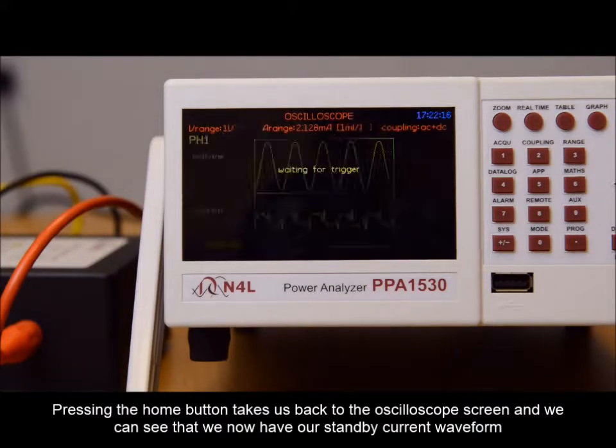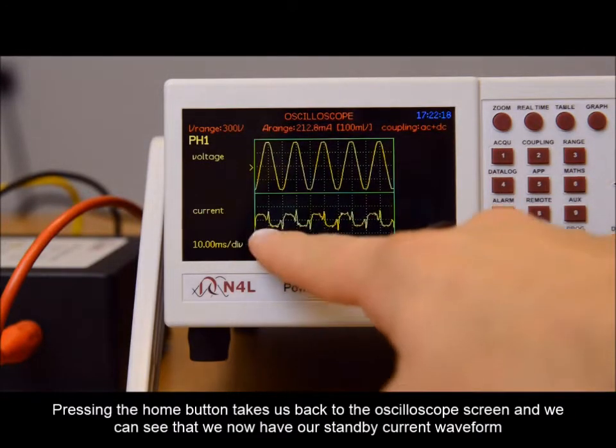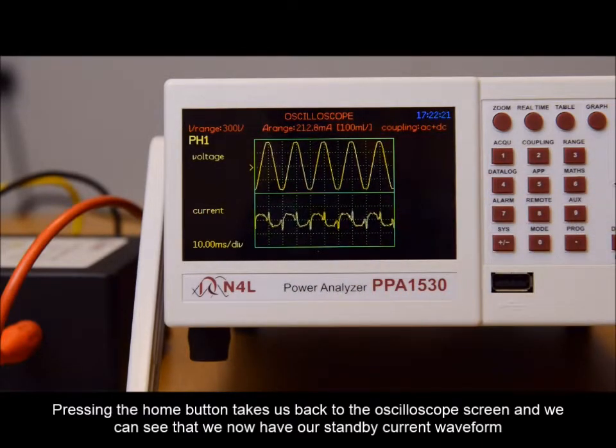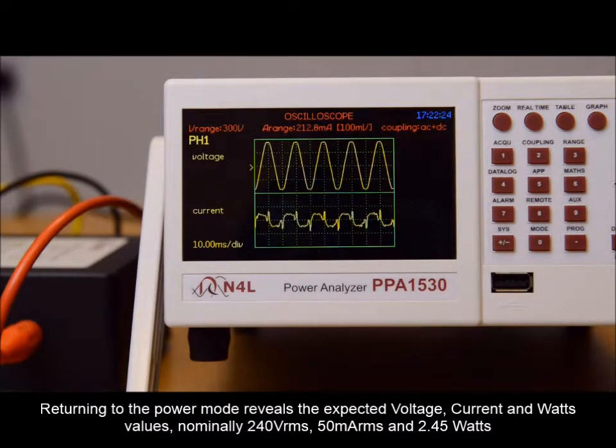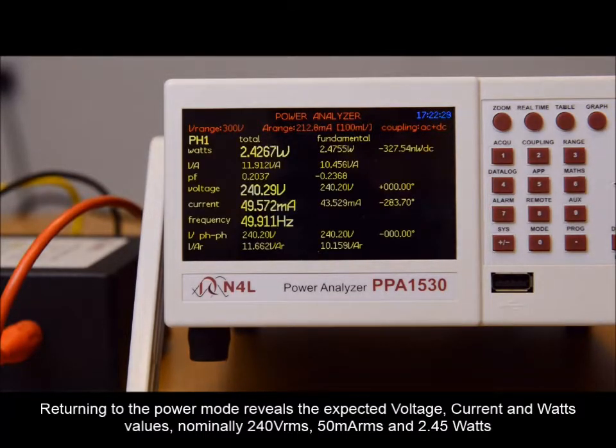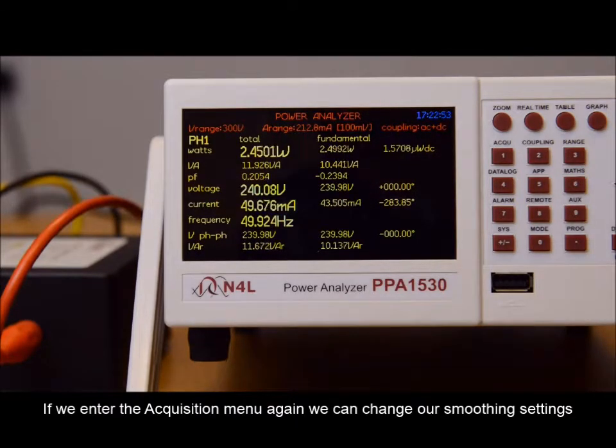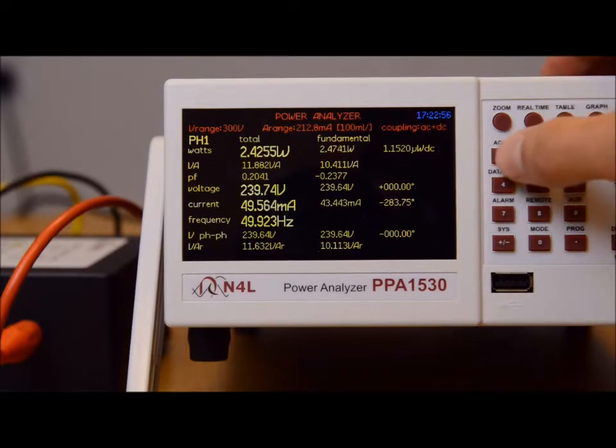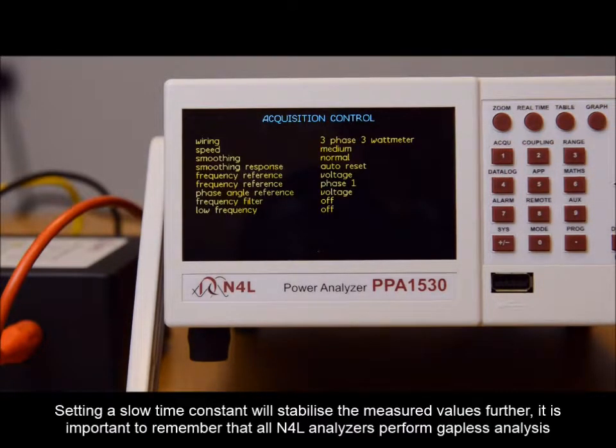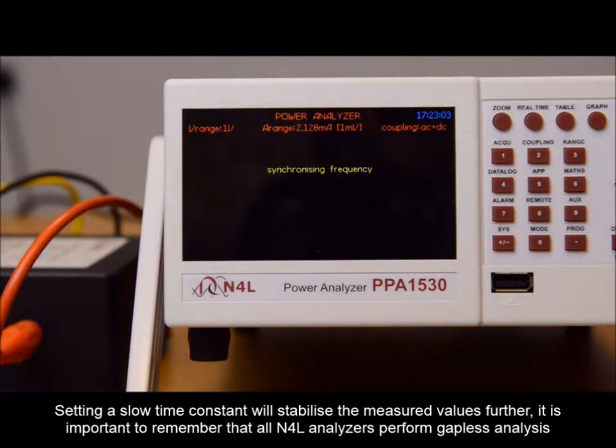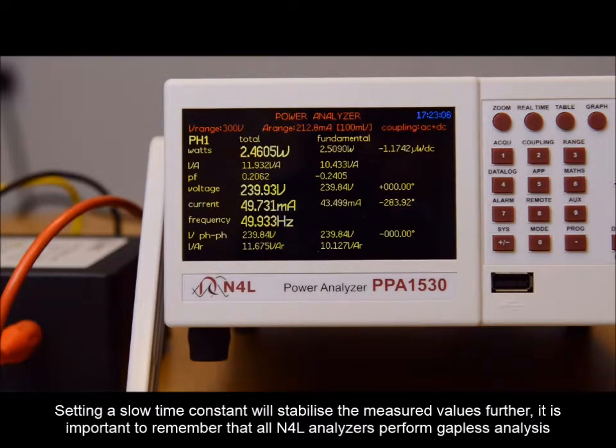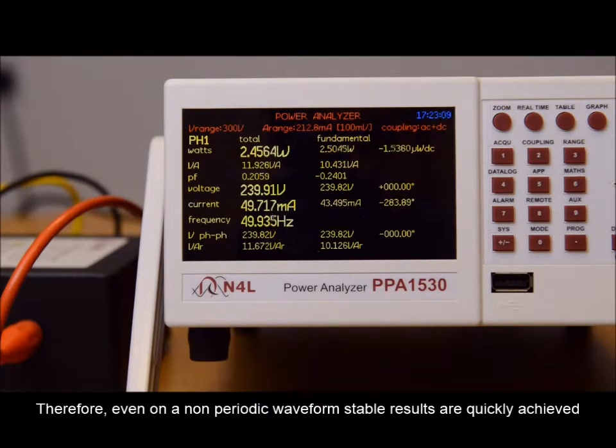Pressing the home button takes us back to the oscilloscope screen, and we can see that we now have our standby current waveform. Returning to the power mode reveals the expected voltage, current and watts values, nominally 240 volt RMS, 50 milliamp RMS and 2.45 watts. If we enter the acquisition menu again, we can change our smoothing settings. Setting a slow time constant will stabilize the measured values further. It is important to remember that all N4L power analyzers perform gapless analysis. Therefore, even on a non-periodic waveform, stable results are quickly achieved.